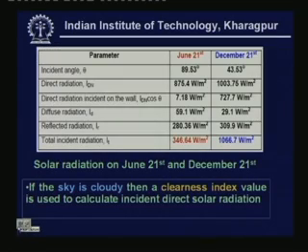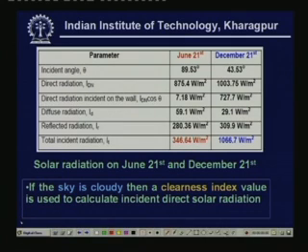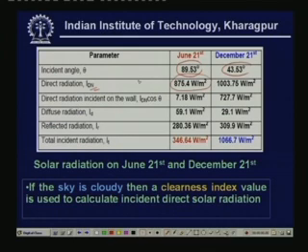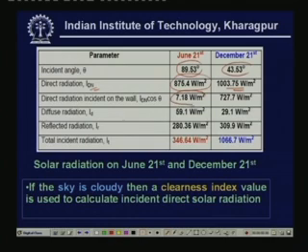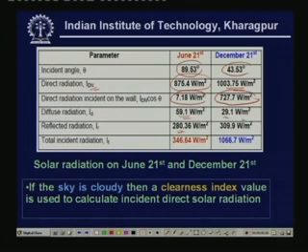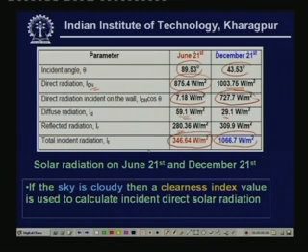This table shows the comparison between June 21st and December 21st. The incidence angle is 89.53° in June and 43.53° in December. I_DN is 875.4 W/m² in June and 1003.75 W/m² in December. The direct radiation contribution I_DN × cos(theta) is 7.18 W/m² for June and 727.7 W/m² for December. Diffuse radiation is 59.1 and 29.1 W/m², reflected radiation is 280.36 and 309.9 W/m², and total incident radiation is 346.64 W/m² in June and 1066.7 W/m² in December.